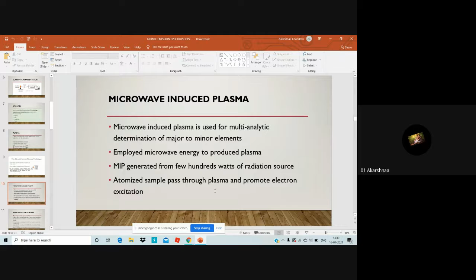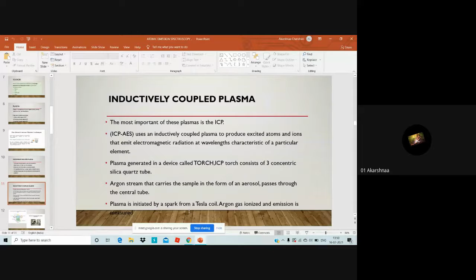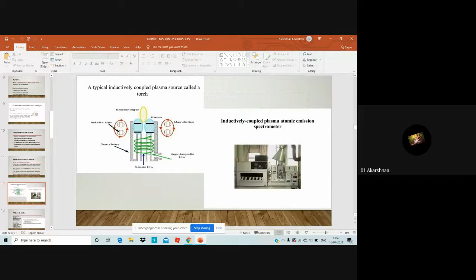And about inductively coupled plasma, that is ICP, it is the most important of these plasmas. It uses an inductively coupled plasma to produce excited atoms and ions that emit electromagnetic radiation at wavelengths characteristic of a particular element. Plasma is generated in a device called a torch. The ICP torch consists of three concentric silica quartz tubes. An argon stream that carries the sample in the form of an aerosol passes through the central tube. Plasma is initiated by a spark from the Tesla coil. Argon gas is ionized and emission is measured. You can see this in the image. And this is the ICP spectrometer.